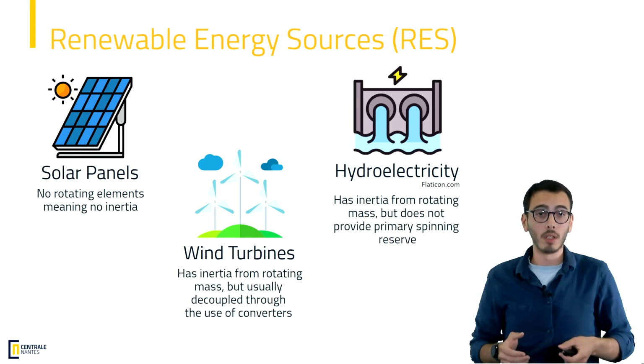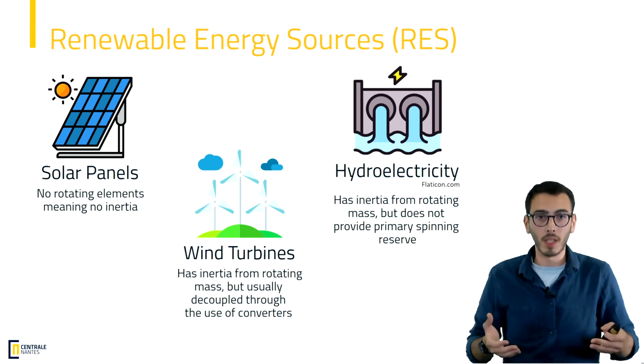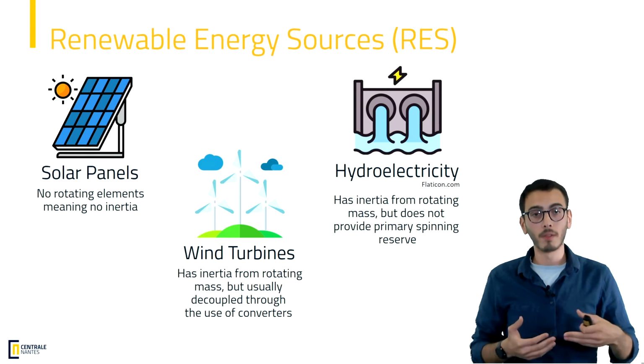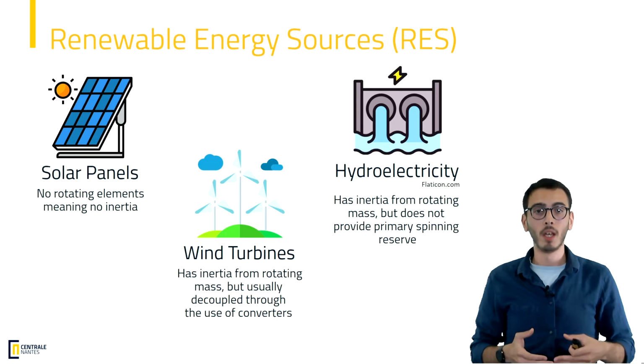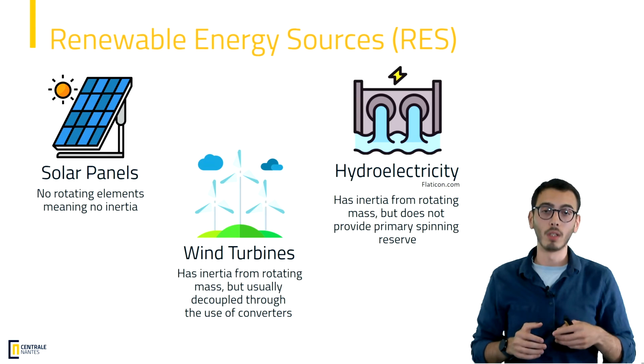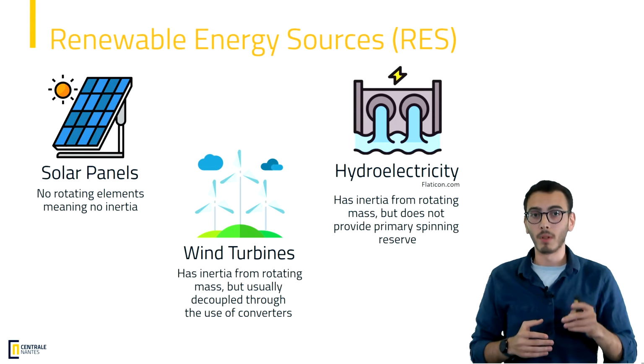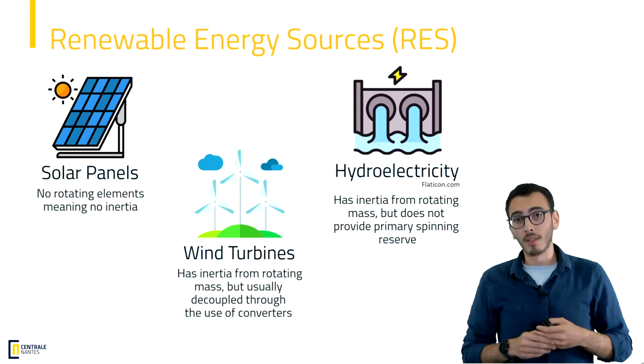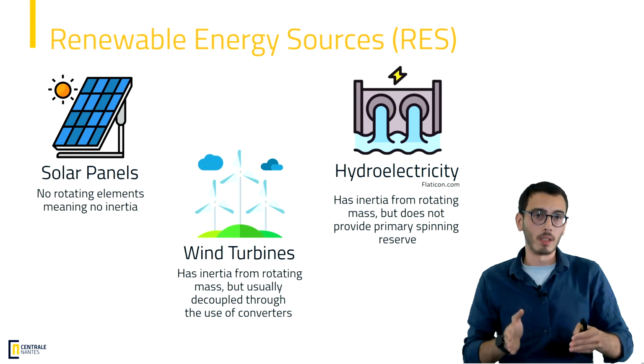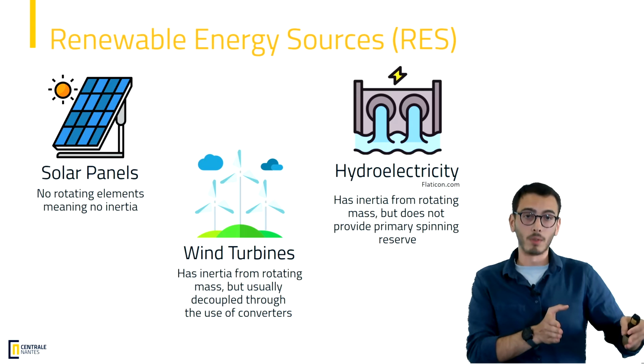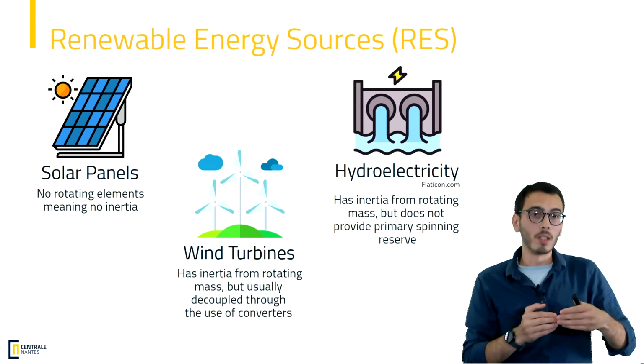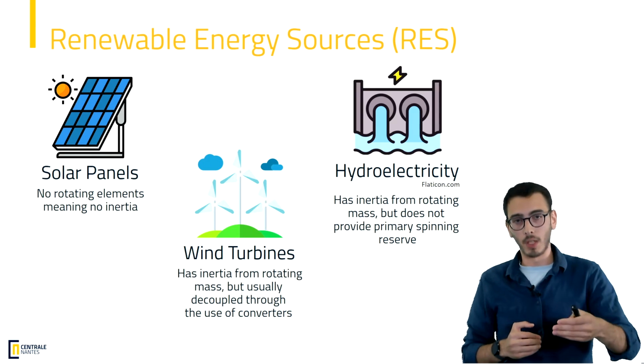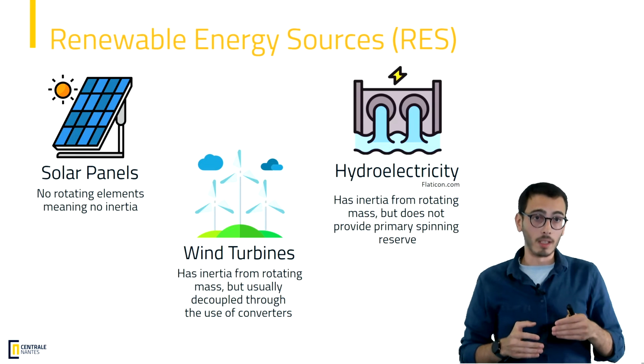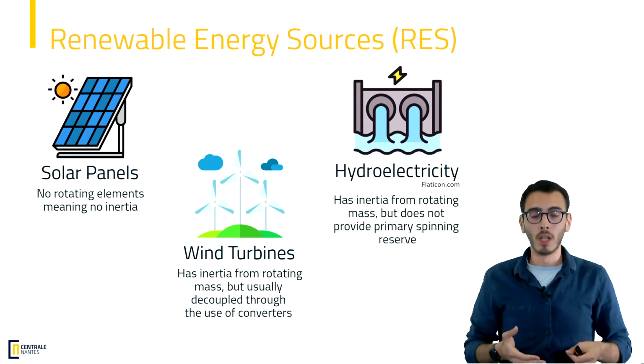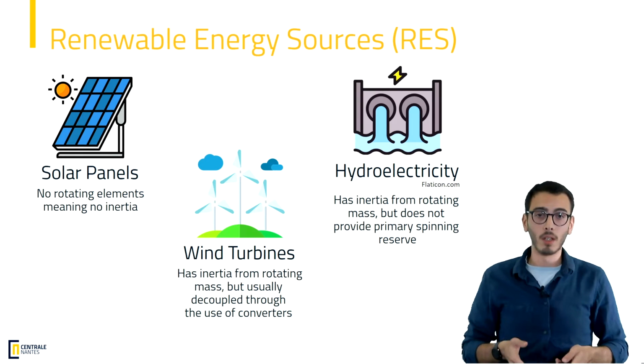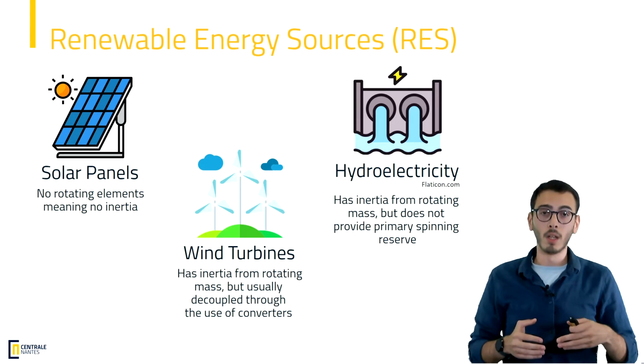In terms of hydroelectricity, well, it actually runs on turbines. So there is a rotating element, there is inertia in these rotating elements. We can benefit from this inertia in our system to improve its stability. But the problem with hydroelectricity is that it does not provide any primary spinning reserve. Primary spinning reserve is, as I explained for the diesel engine, if I'm at 50% load, it means that I still have 50% load ready to be used with a certain ramp-up speed. The problem with hydroelectricity is that if I demand more power from this plant, it's going to take a lot of time to increase this power. So it's not effectively adding to the stability, because if I demand power, I require it right now, not after 10 minutes. So you see where the difficulty in stability brought by hydroelectricity comes from.